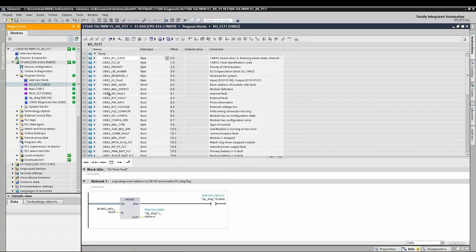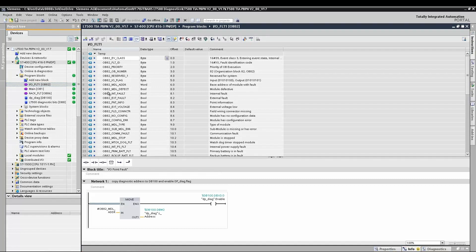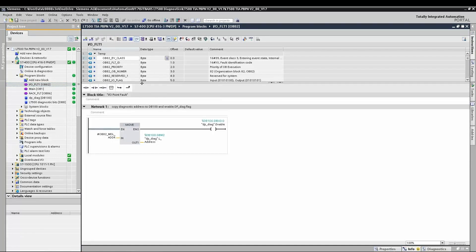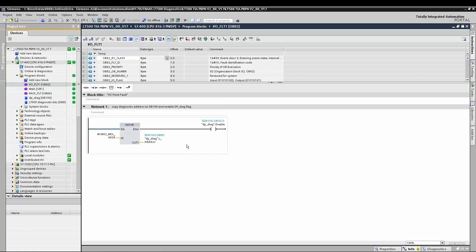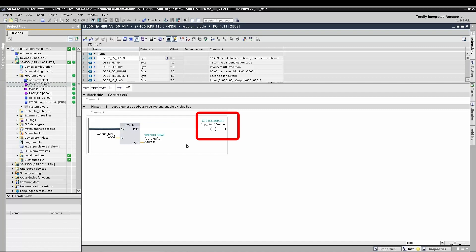So how do we capture those diagnostics in the S7-400? The S7-400 has special organizational blocks which are responsible for capturing such diagnostics. In this example, OB82 is being used, and we're copying the diagnostic address of the module which calls the diagnostic and we're also setting the dp-diag bit.